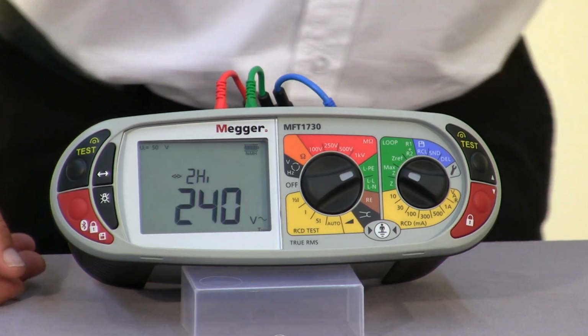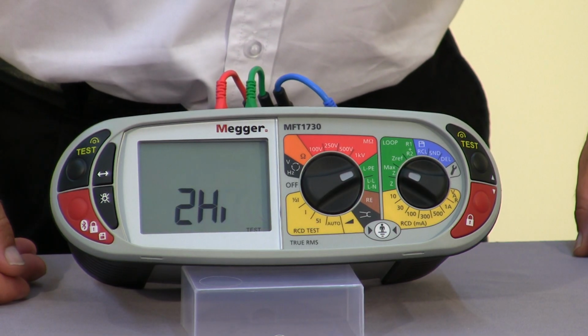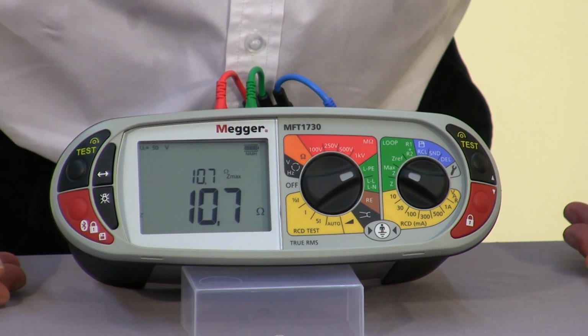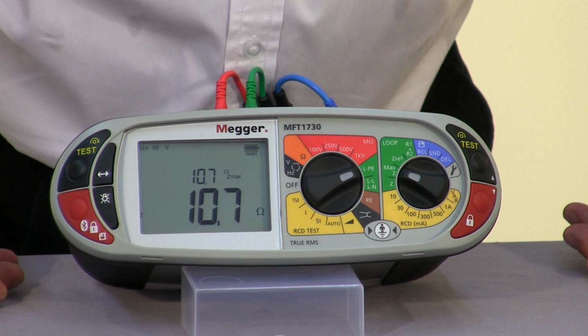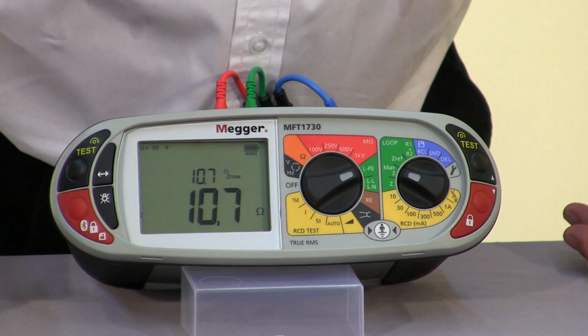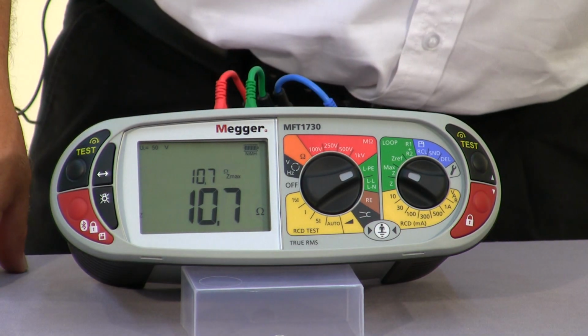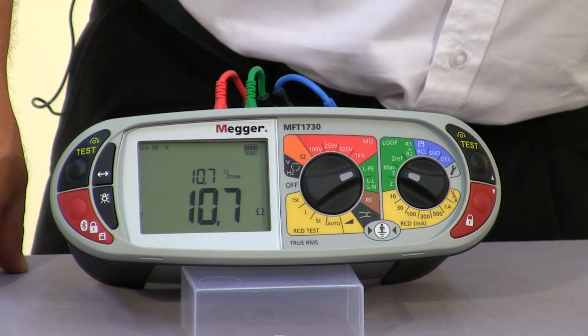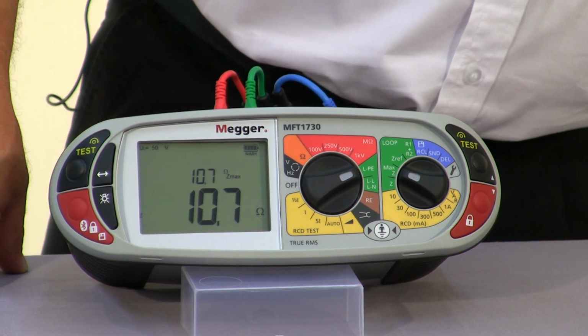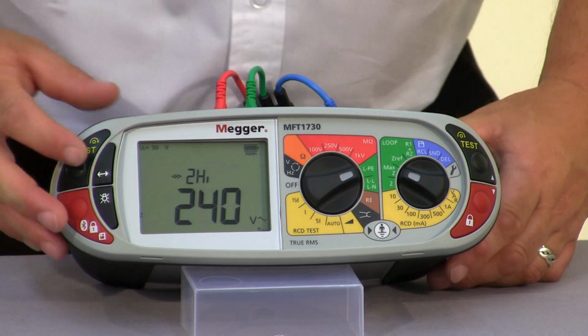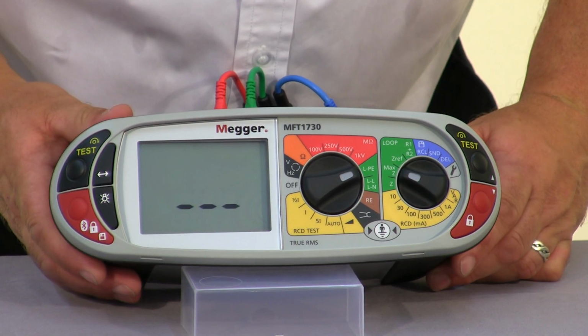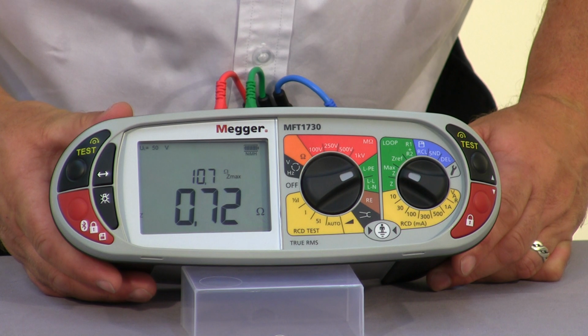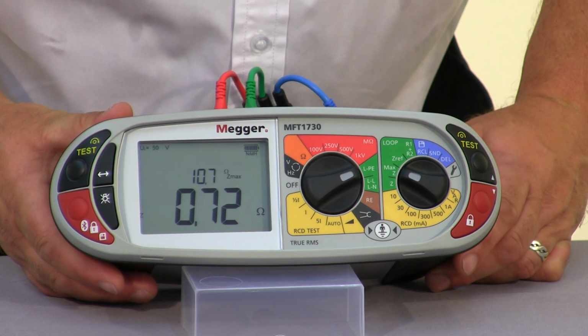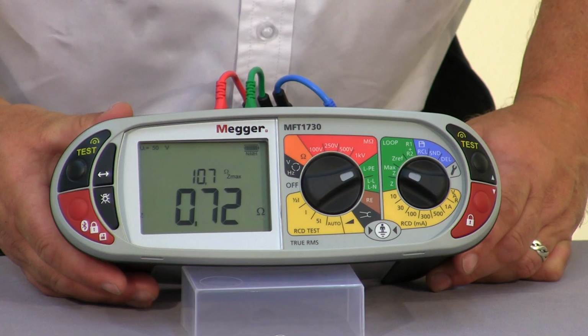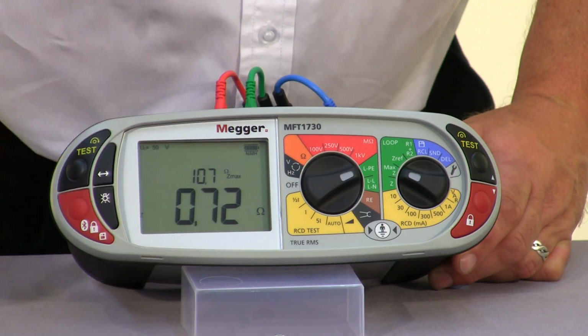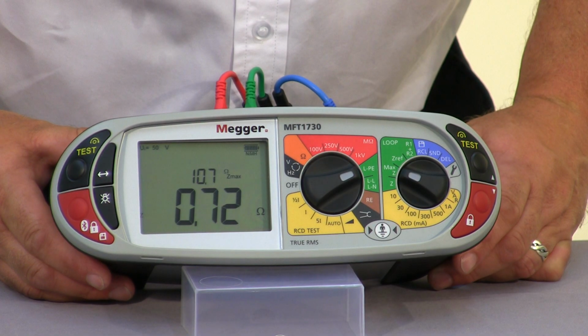The unit is set to auto start, and you'll see that the reading we've achieved is 10.7 ohms. Now you'll notice that that is actually repeated on the upper of the two displays. So when we select a retest, so we go to our second socket, it automatically tests, and you'll see here we've got 0.72 of an ohm. So the original reading, which had the simulated extra 10 ohms in it, as you can see, is still retained on the upper of the two displays.